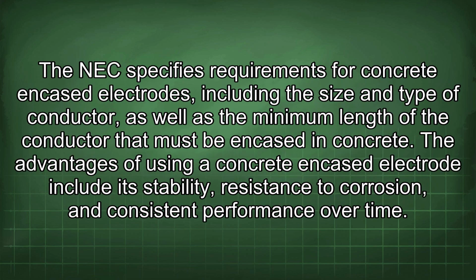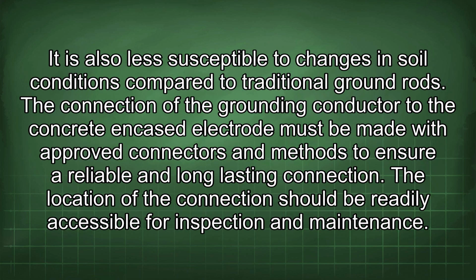The NEC specifies requirements for concrete encased electrodes, including the size and type of conductor, as well as the minimum length of the conductor that must be encased in concrete. The advantages of using a concrete encased electrode include its stability, resistance to corrosion, and consistent performance over time. It is also less susceptible to changes in soil conditions compared to traditional ground rods. The connection of the grounding conductor to the concrete encased electrode must be made with approved connectors and methods to ensure a reliable and long-lasting connection. The location of the connection should be readily accessible for inspection and maintenance.